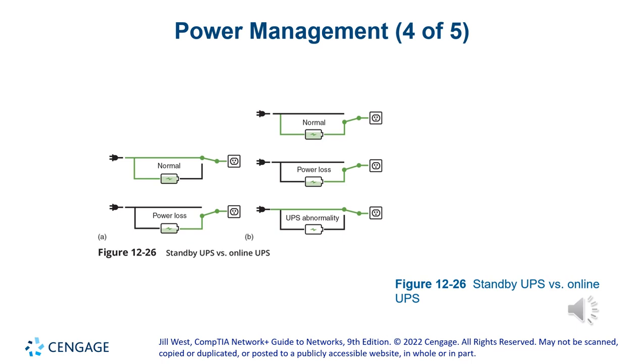Sometimes you want to bypass your UPS, so you go straight from the power company power for maintenance, battery replacement, or anything like that. Then you can flip the switch into maintenance mode, which will go straight. The problem with that is, with any lightning at that moment, you have no UPS. But you do it at a time, like in the morning or on a weekend, where you don't expect the power to flicker. But if it does, then there's nobody in your area.